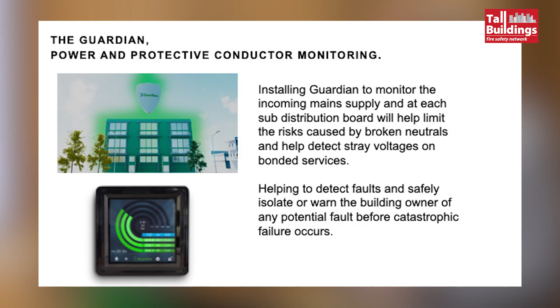This instance here is a unit that was installed on C2C railway. As soon as it was installed, it told them there was a stray voltage present. They went out and tested, and they tested 35 volts on a sign on the main pedestrian walkways. In the right instance, rain, someone with a pacemaker, etc., could cause a massive problem for that person.